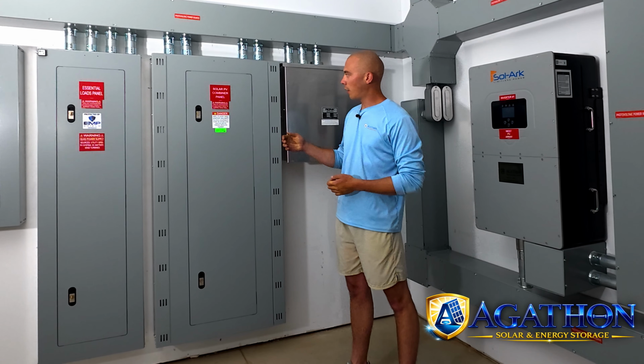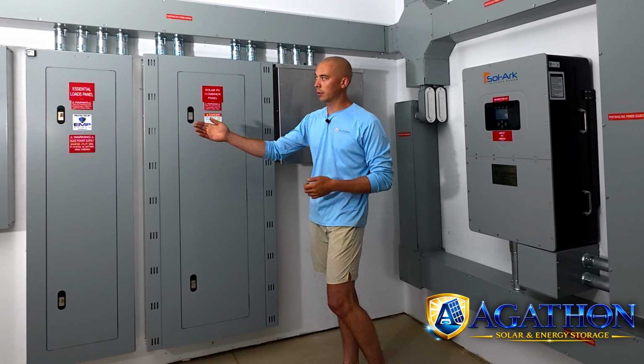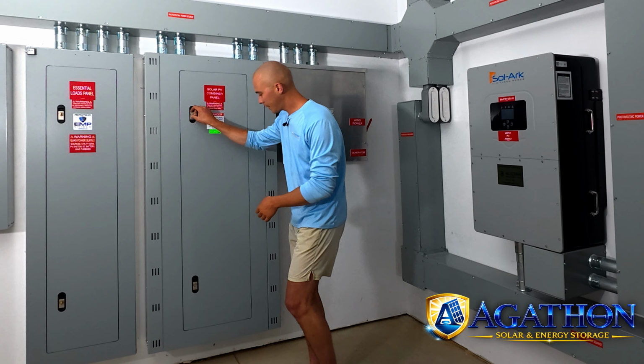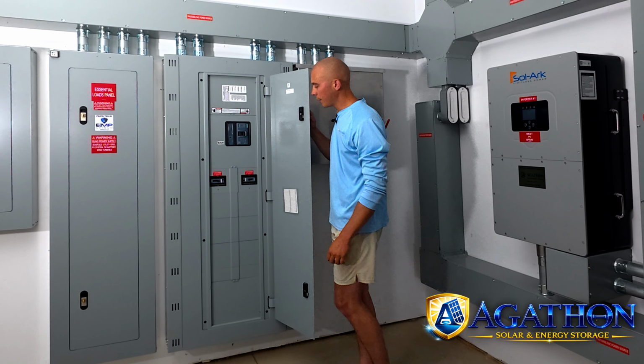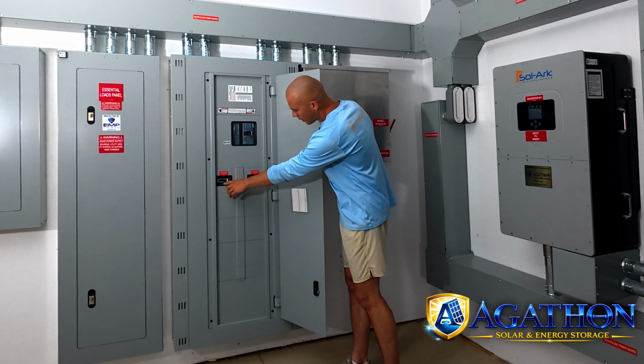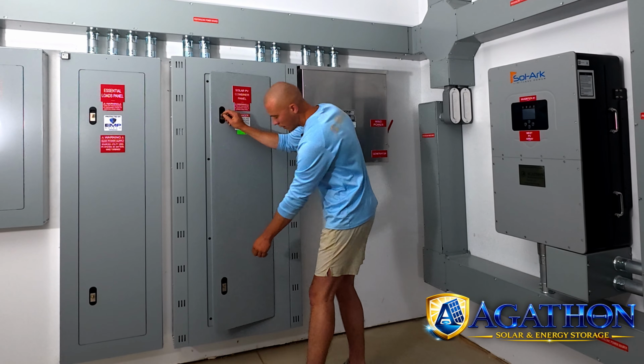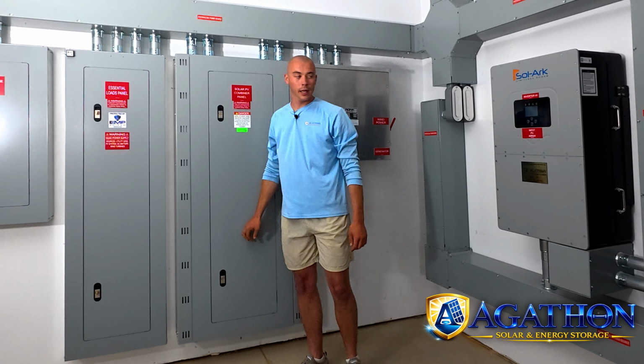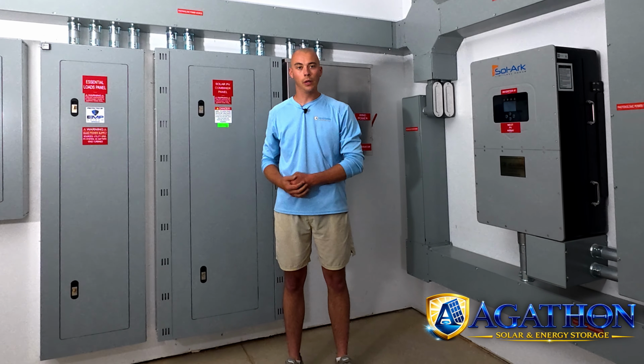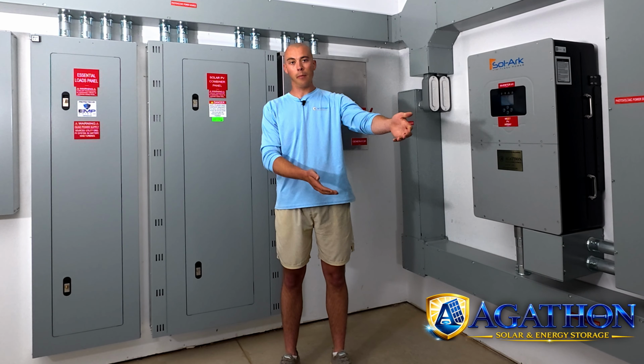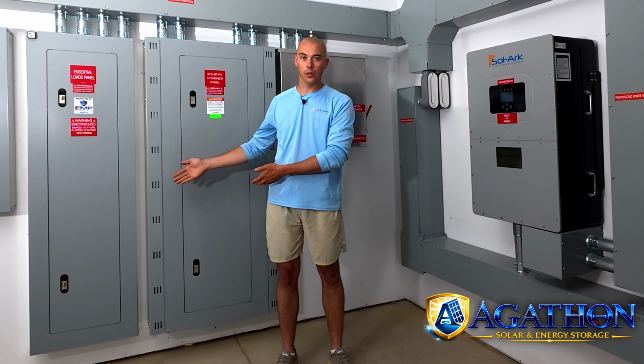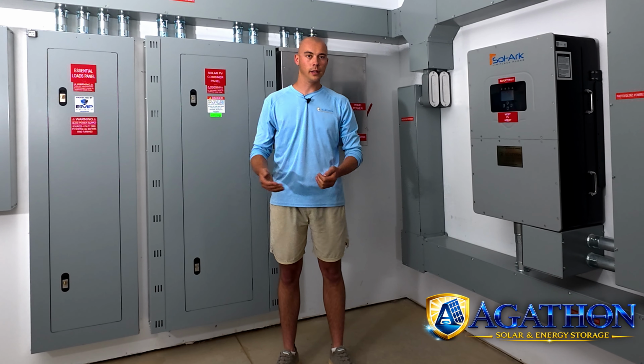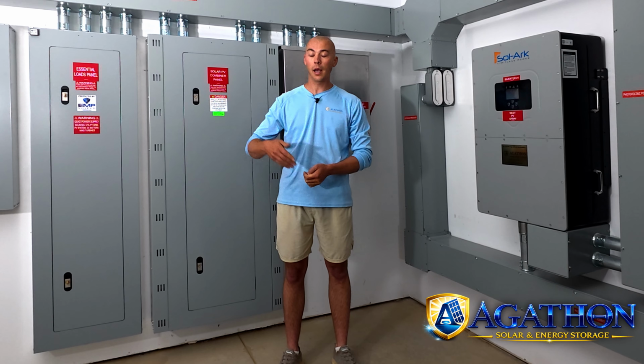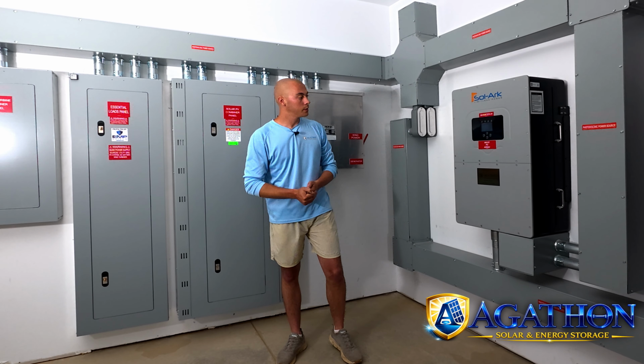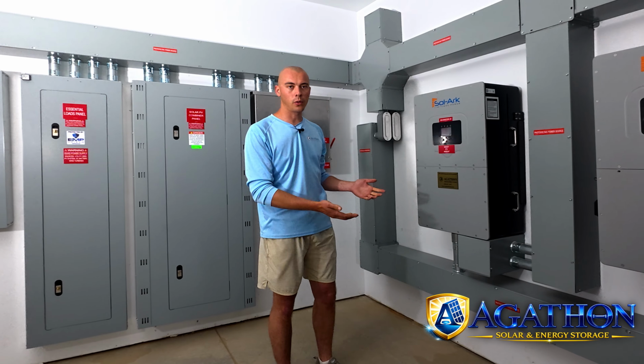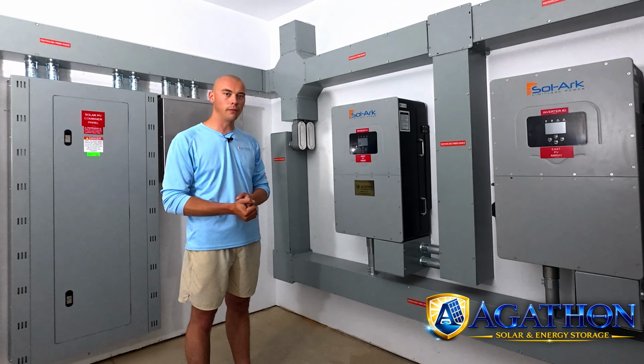Now here we have our solar PV combiner, similar to the wind turbine combiner. This combiner takes in the power of both Sol-Ark 30K inverters through these two breakers here, and again is distributed similar to the wind turbine combiner panel to either the batteries to charge those, provide power to the home and the essential loads panel, and again in the event of excess generation, exported back to the utility. Speaking of solar PV, these are our two Sol-Ark 30K 208 volt hybrid inverters.